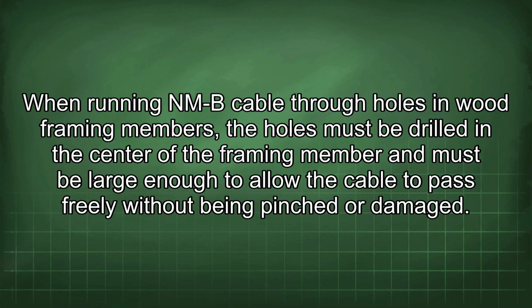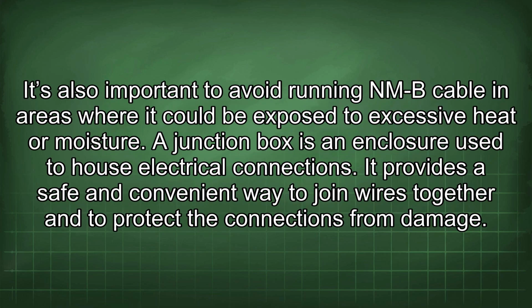When running an NMB cable through holes in wood framing members, the holes must be drilled in the center of the framing member and must be large enough to allow the cable to pass freely without being pinched or damaged. It's also important to avoid running an NMB cable in areas where it could be exposed to excessive heat or moisture. A junction box is an enclosure used to house electrical connections.